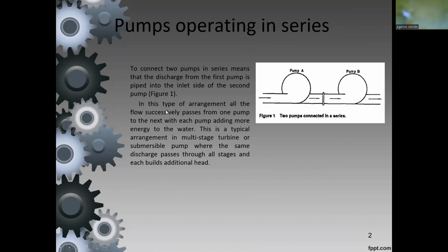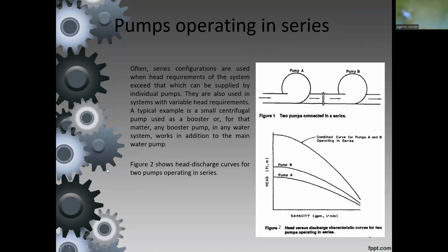Unahin natin yung series. In this type of arrangement, all the flow successively passes from one pump to the next, with each pump adding more energy to water. This is a typical arrangement in multi-stage turbine or submersible pump, where the same discharge passes through all stages and each builds additional head. Yung flow rate the same, yung head ang nagdadagdag. Often, series configurations are used when head requirements of the system exceed that which can be supplied by an individual pump. So, magdadagdag ka. Yung head required ng isang pump kulang, so magdadagdag ka.